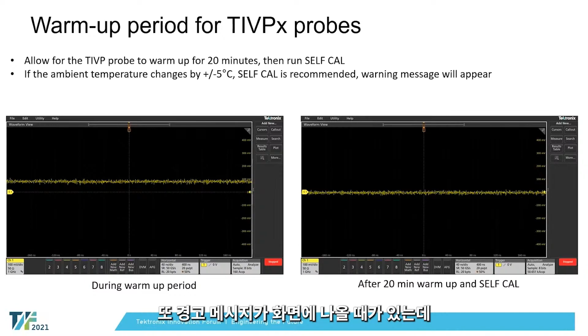And you'll see the effects of that warm-up period are very apparent from first plug-in. On the left-hand side, I've got a picture of when I just first attached IsoVu to my scope. You'll see that there's a DC offset, again, apparent with really any differential probe that you plug in that's cold or is at a different ambient temperature from when it was last auto-zeroed. And then after 20 minutes and after running the self-calibration piece built into the scope, sure enough, that DC offset goes away. There's also a warning that comes up if the ambient temperature around the probe changes by plus or minus 5 degrees C. We recommend that if the ambient temperature changes by that amount, that you recalibrate the probe. There will also be a warning message that comes up on the screen indicating that we recommend, again, that you run the self-calibration routine.